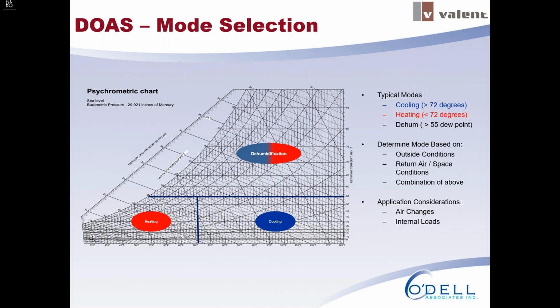So a typical cooling set point would be 72 degrees Fahrenheit. Anything above that, you'd be in cooling mode. Anything below that, you'd be in heating mode. And then a dehumidification set point is right around 55 degrees dew point. And again, those are all adjustable depending on the application. And those temperatures could be outside temperatures, they could be space temperatures that you're measuring, or it could be a combination. So all those factors can be adjusted or tweaked depending on what the application calls for.